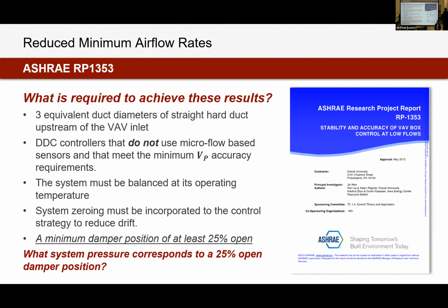We also have to use a specific type of controller on that damper that can measure velocity pressures down that low. Most commodity modern day controllers actually can't even pick up velocity pressure that low. So you have to use a specific type of controller. The system had to be balanced at that low operating point. And usually you're only balancing to a maximum. And then finally in this report, they were auto zeroing between every single reading. Most systems are not designed to auto zero daily, especially not hourly. So you're using like an Ashcroft kind of automatic auto zero, like an $800 pressure transducer kind of a thing. Basically, yes. Again, this was a research report, so they were using the best of the best equipment to run it.